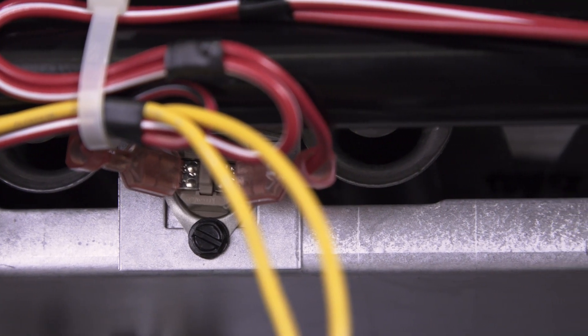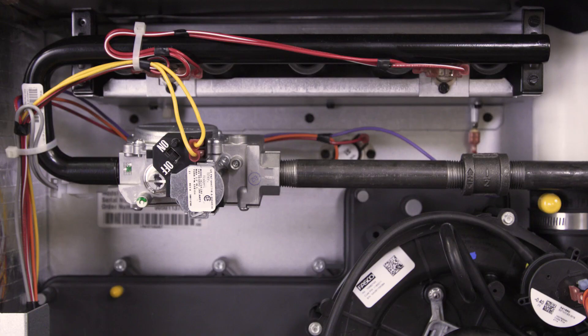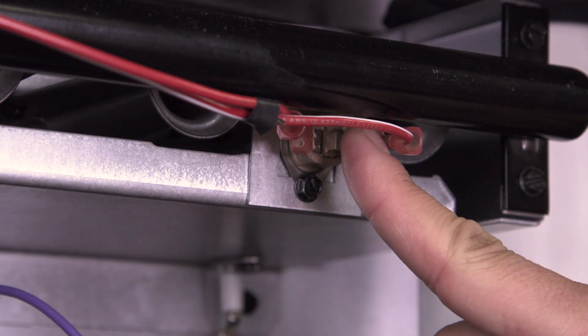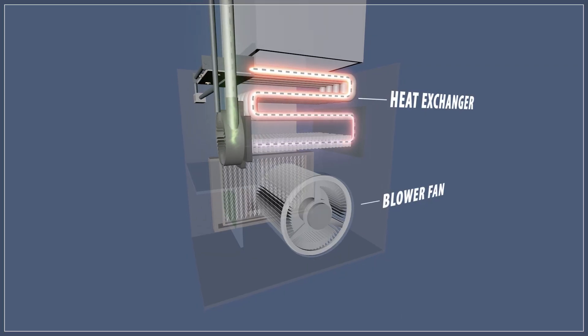Look for any scorch marks, as this indicates a more serious problem. If the flames roll out the front of the burner, the flame rollout switch shuts off the furnace. These switches usually have a reset button. If you reset the switch and the switch keeps tripping, then shut your furnace off and call a professional. The heat exchanger could be cracked and could be releasing carbon monoxide into your home.